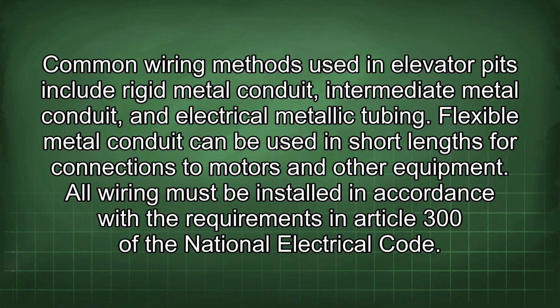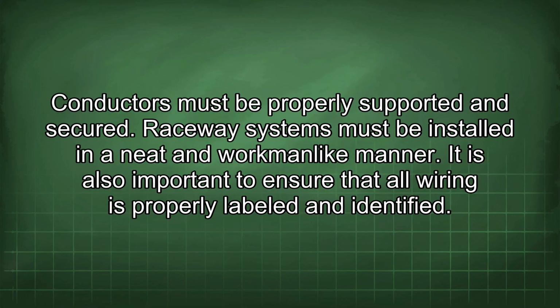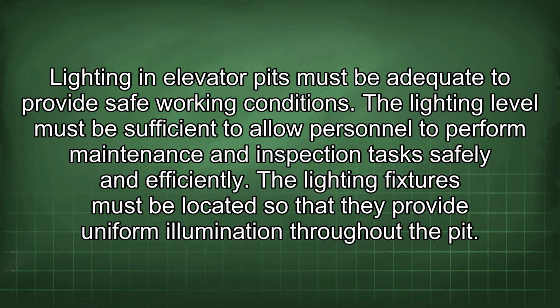All wiring must be installed in accordance with the requirements in Article 300 of the National Electrical Code. Conductors must be properly supported and secured. Raceway systems must be installed in a neat and workmanlike manner. It is also important to ensure that all wiring is properly labeled and identified. Lighting in elevator pits must be adequate to provide safe working conditions. The lighting level must be sufficient to allow personnel to perform maintenance and inspection tasks safely and efficiently.